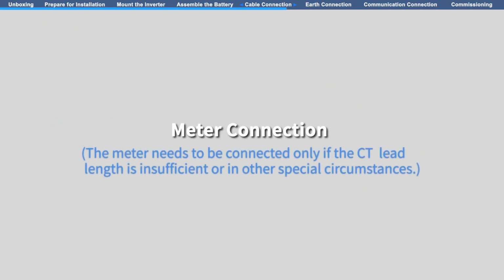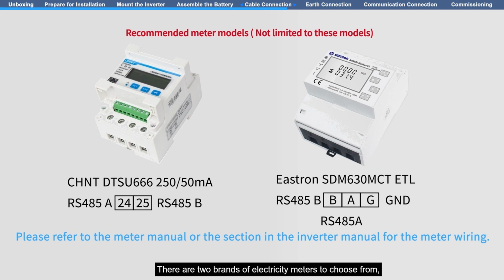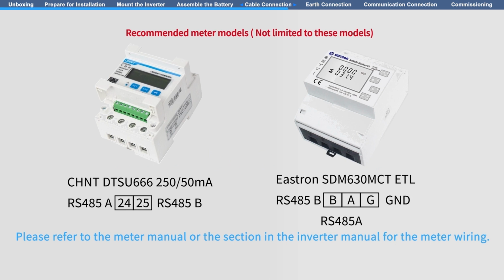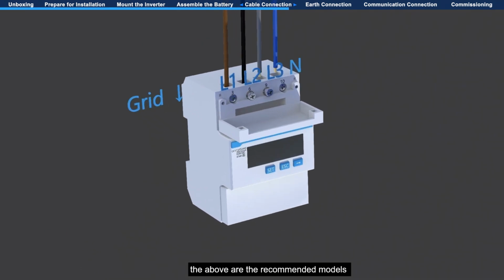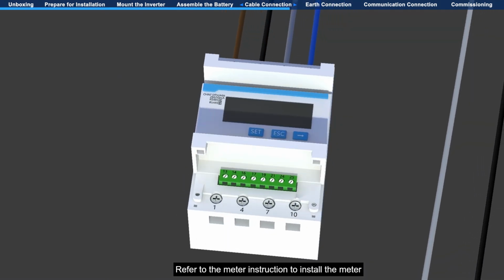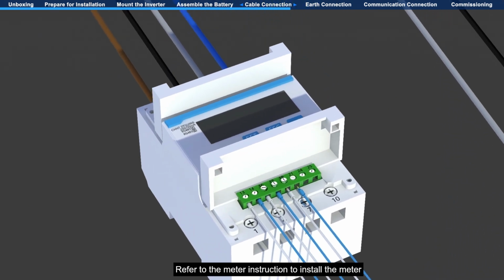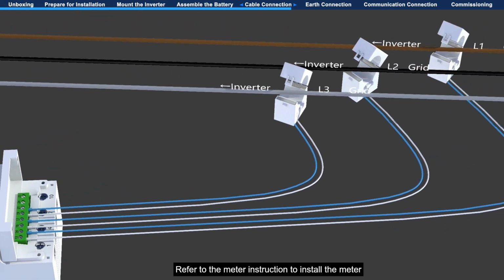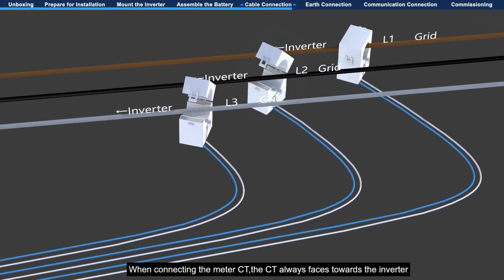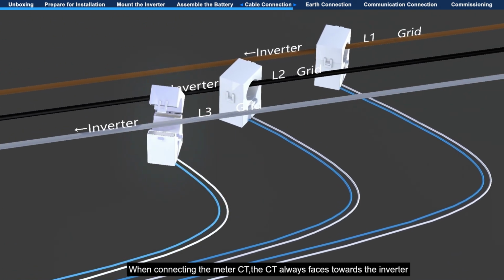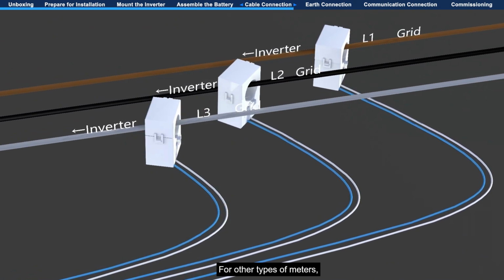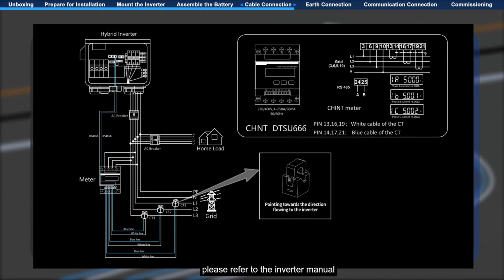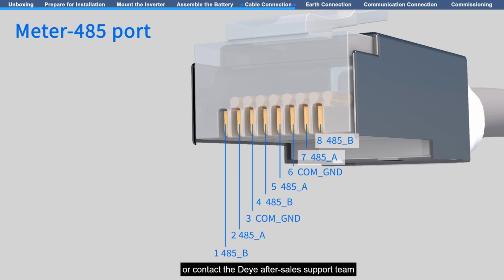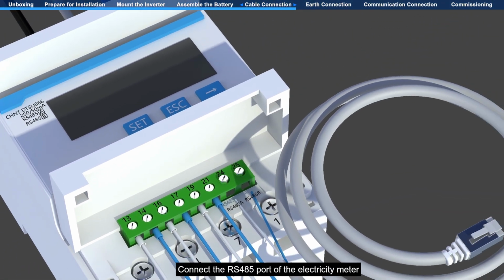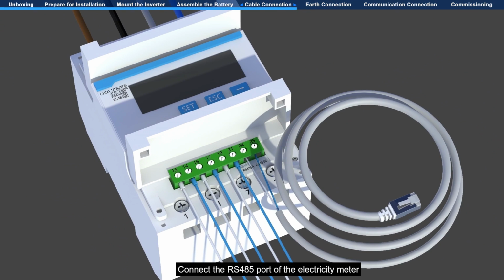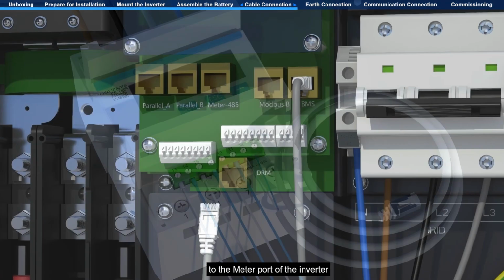Meter connection. There are 2 brands of electricity meters to choose from. The above are the recommended models. Refer to the meter instruction to install the meter. When connecting the meter CT, the CT always faces towards the inverter. For other types of meters, please refer to the inverter manual or contact the Deye after-sales support team. Connect the RS-485 port of the electricity meter to the meter port of the inverter.